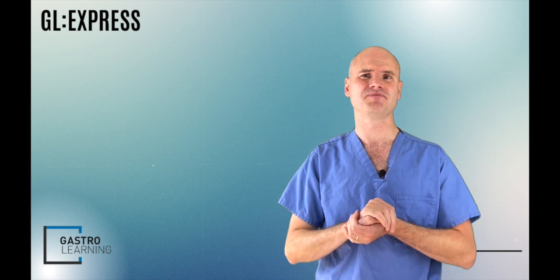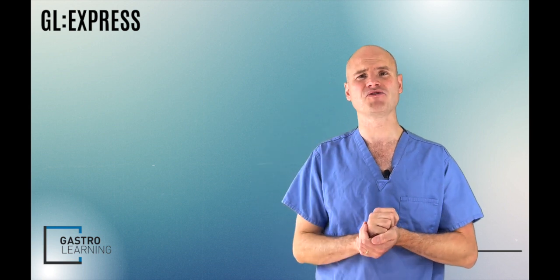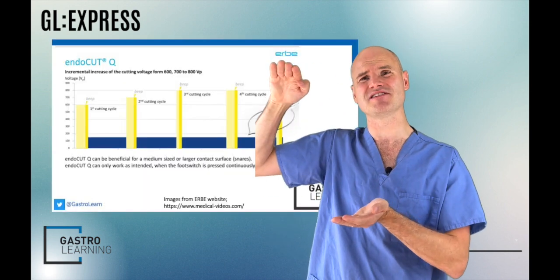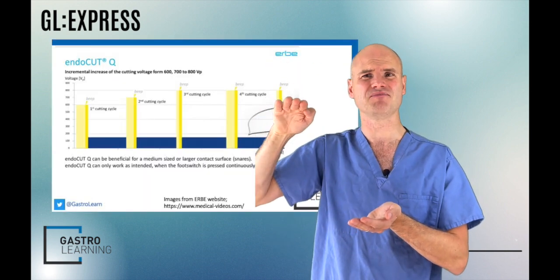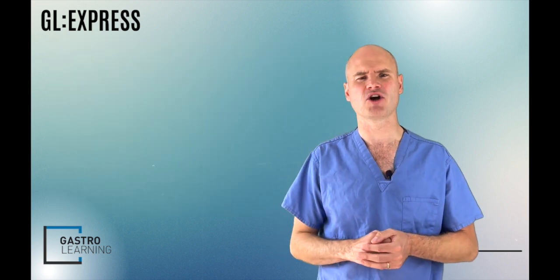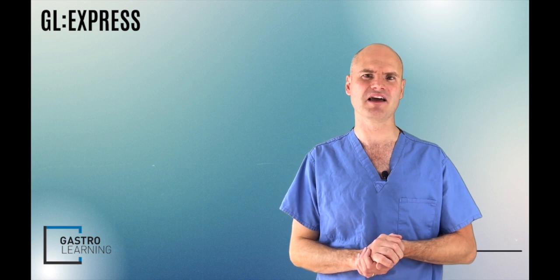The last thing I will say is that in Endocut I setting, there is no stepwise increase in the voltage. It stays at a constant level. So I hope this helped. We'll do another video on the coagulation settings, and I'll hand over to my colleague at some point and let him talk about the cutting and coagulation settings for ERCP work.